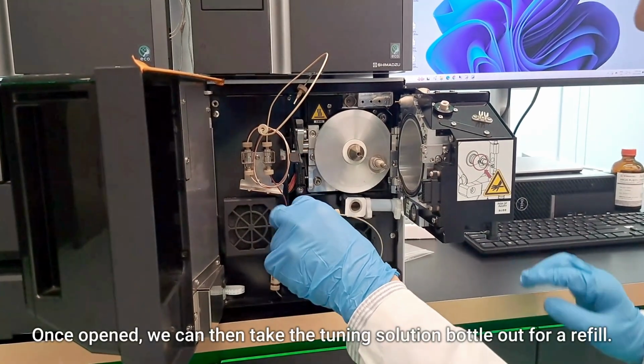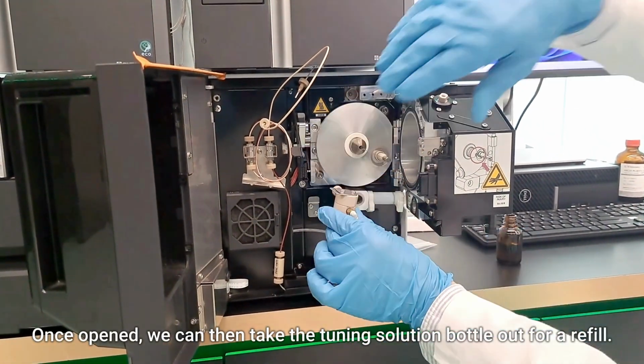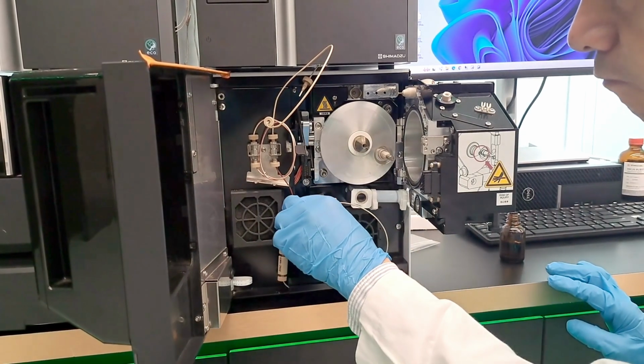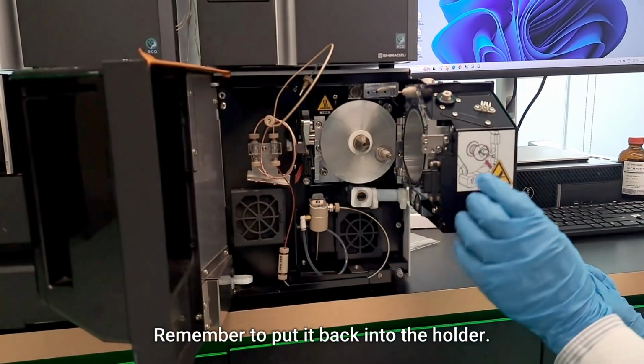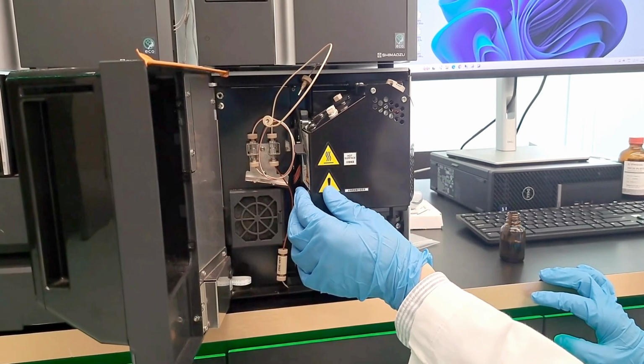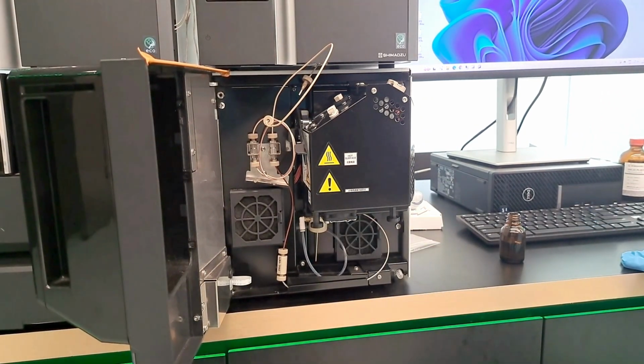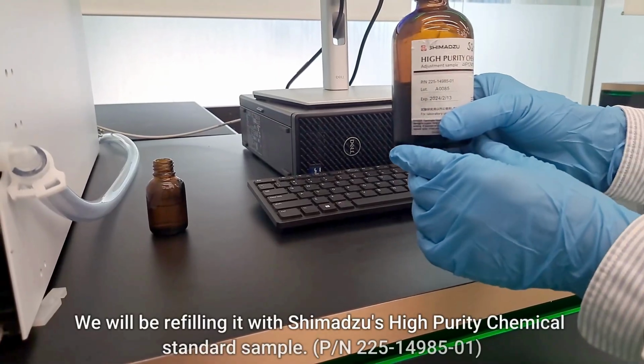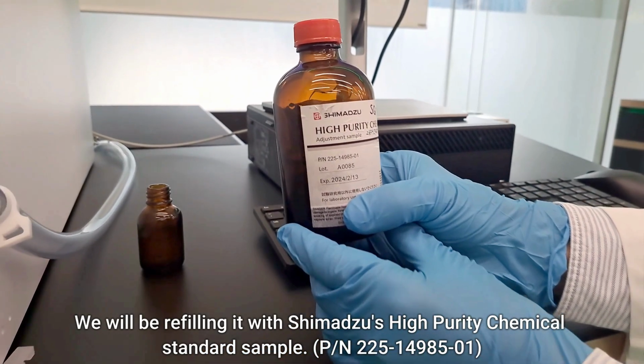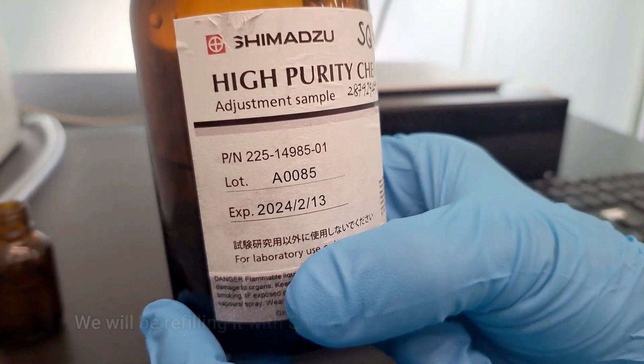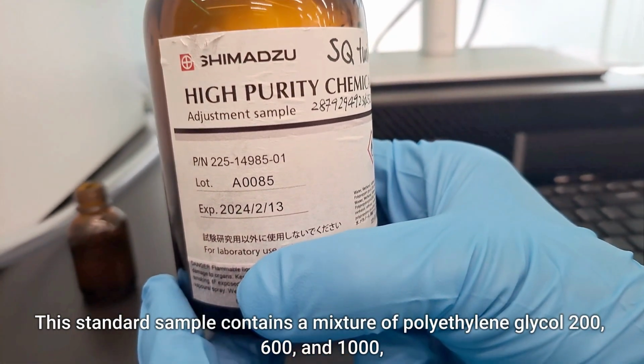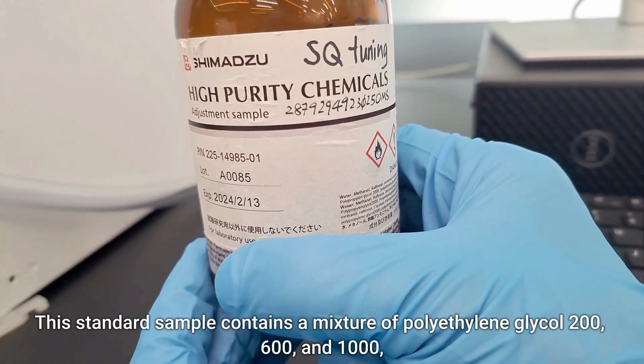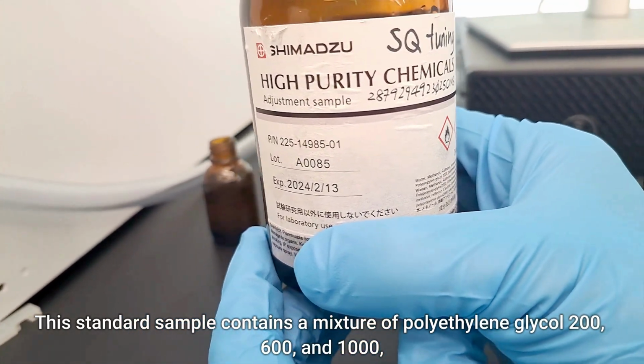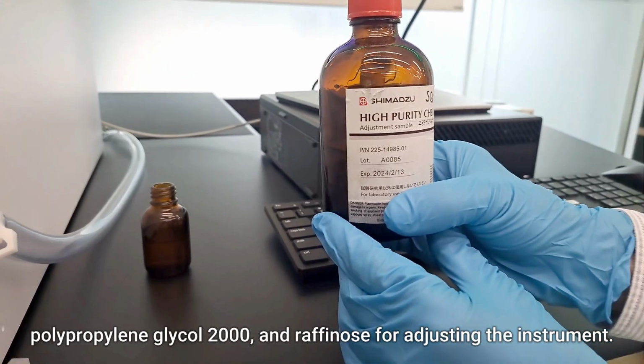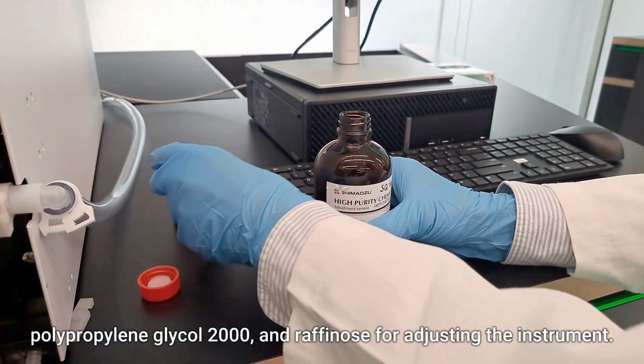Once opened, we can then take the tuning solution bottle out for a refill. Remember to put it back into the holder. We will be refilling it with Shimadzu's high purity chemical standard sample. This standard sample contains a mixture of polyethylene glycol 200, 600, and 1000, polypropylene glycol 2000, and raffinose for adjusting the instrument.